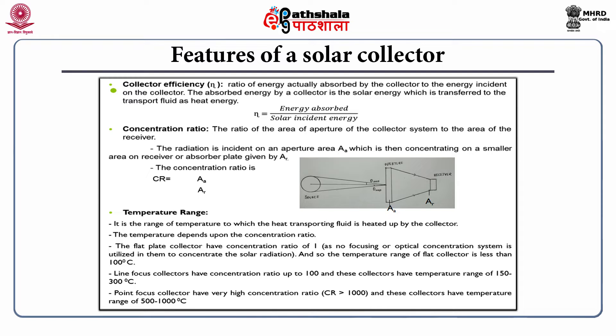The third feature is the temperature range — the range of temperature to which the heat-transporting fluid is heated by the collector. The temperature depends on the concentration ratio. The flat plate collector has a concentration ratio of 1, as there is no focusing or optical concentration system, so its temperature range is less than 100°C. Line focus collectors have a concentration ratio up to 100 and a temperature range of 150 to 300°C. Point focus collectors have a very high concentration ratio with CR greater than 1000 and a temperature range of 500 to 1000°C.